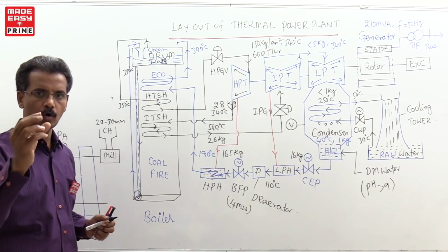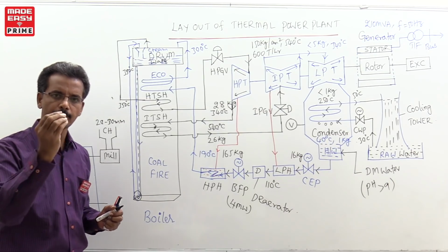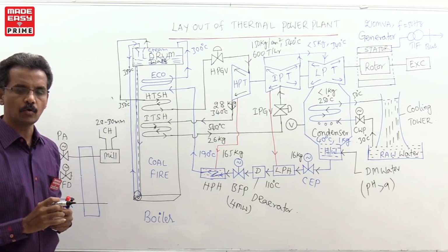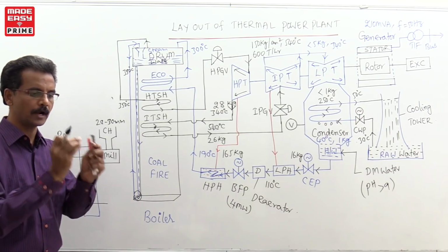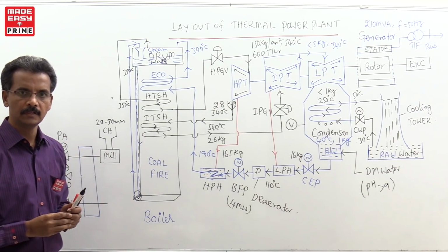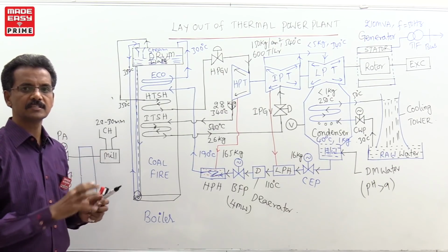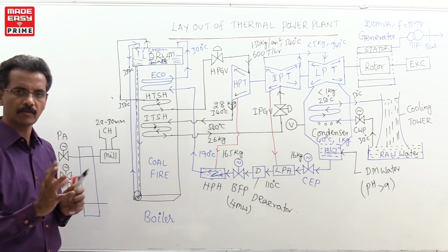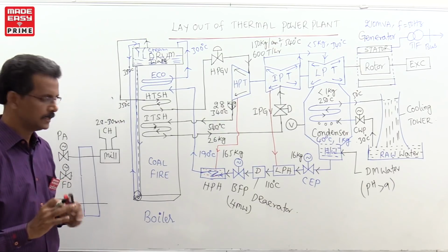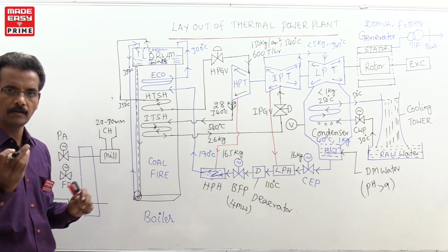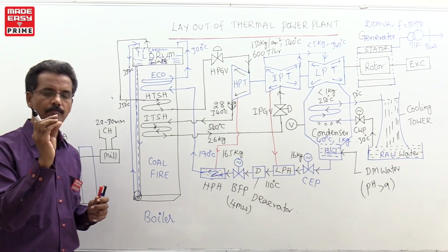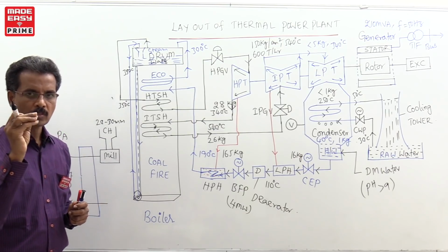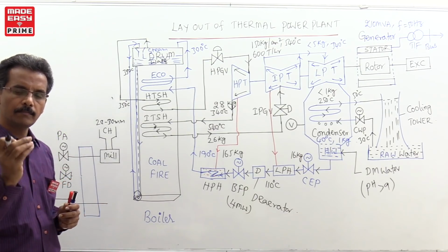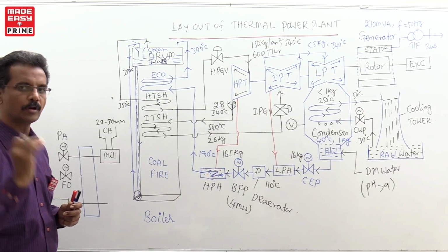coal. Now the coal is converted into fine powder, which is called pulverized coal. The advantage of pulverized coal is that it can burn easily, and the efficiency of the system is improved for faster burning, and faster control also becomes easier. That is the purpose of using this mill, which is used to convert the bigger form of 20 to 30 mm size coal into pulverized or powder format.